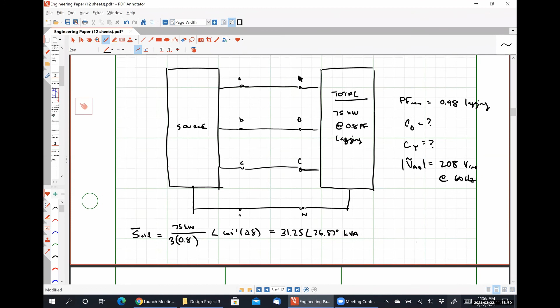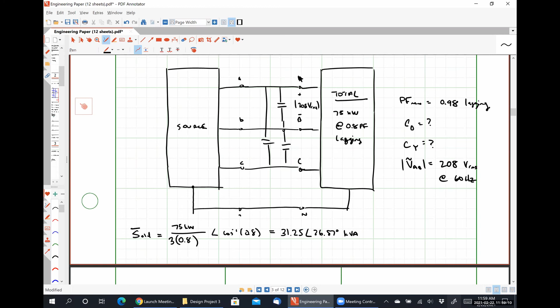Now we need the voltage drop over the capacitor bank, right? For the delta connected bank, that would be like putting it here, here, and here. We know this voltage is 208, so the value of the RMS voltage we'll use is that 208 volts RMS. Square that, and please tell me what number you get.